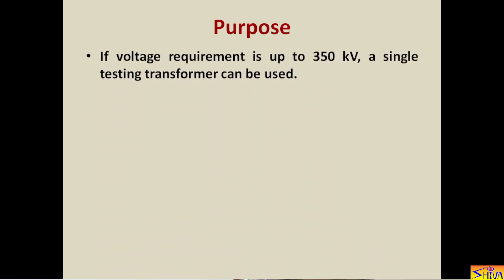In the previous lecture I had explained generation of high AC voltage by a single testing transformer. There were a few limitations or drawbacks of using a single unit for generating high AC voltage. If voltage requirement is up to 350 kV a single testing transformer can be used, but after that the problems become dominant.